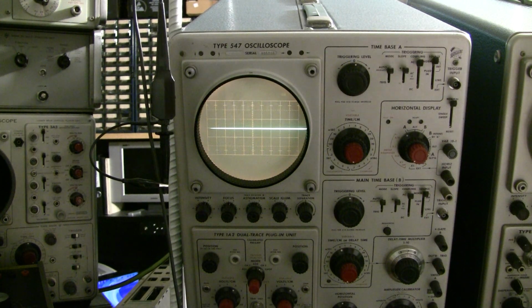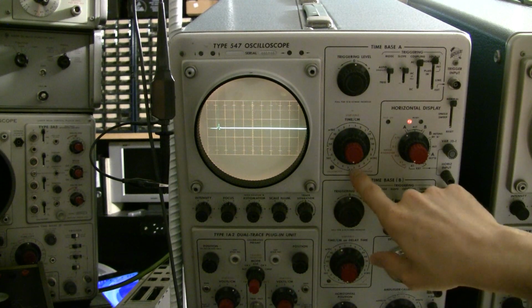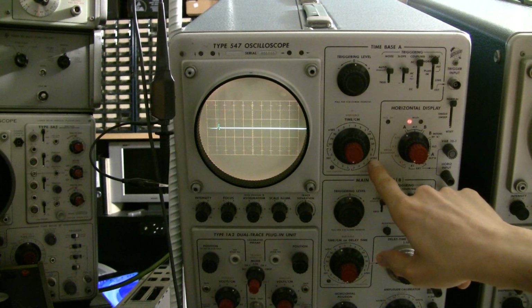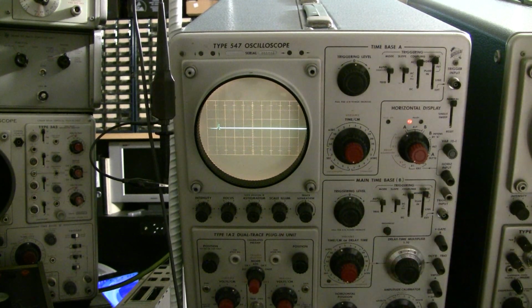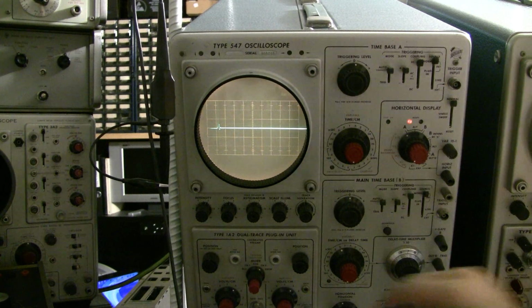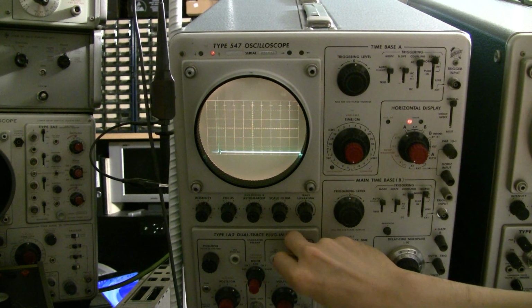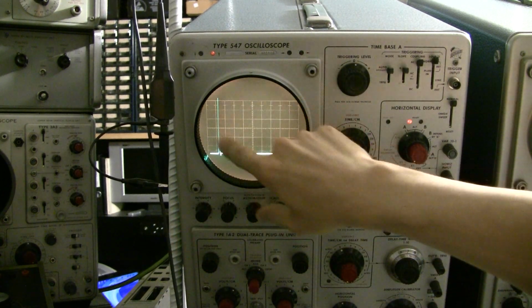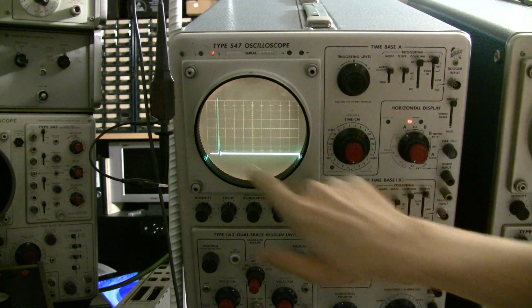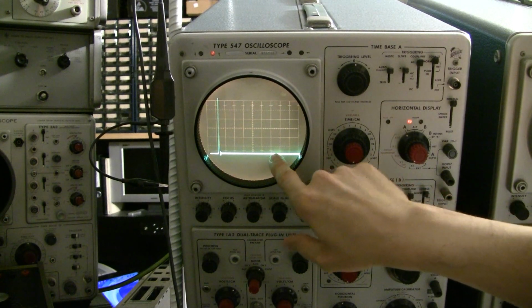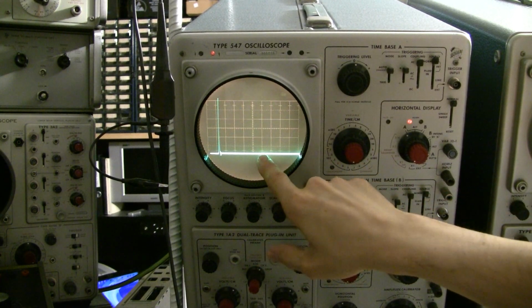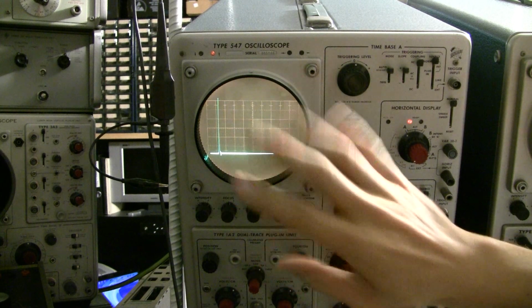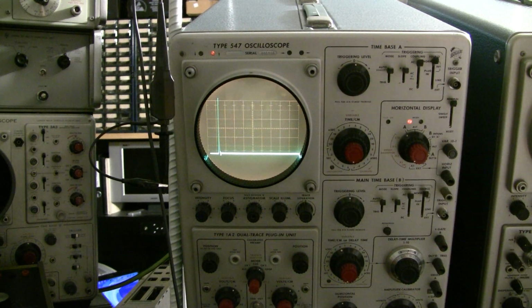So we'll turn on the TDR now. We can already see the pulse at 100 nano. 0.1 microseconds per division is 100 nano per division. So that's in today's speak, 100 nano. So I'll move the vertical position down here and turn the intensity up just a little bit more, and we can see that signal absolutely perfectly. Now this probably looks really bright in the camera, but it's not very bright here. It's comfortable for my eye, and the camera is really sensitive to this phosphor, so that's why it's going to look really bright in the camera.